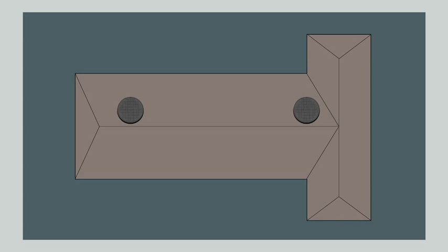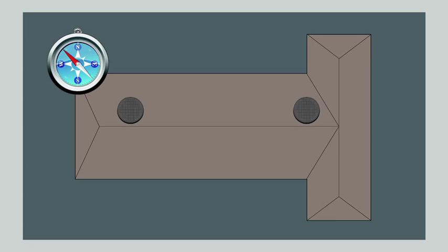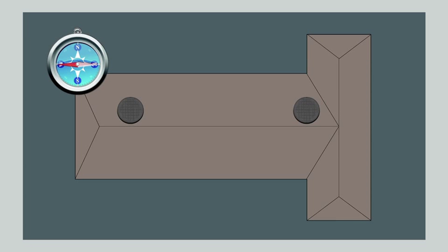The solar fan units are best placed as high as possible on a north facing facade. North east or north west are also acceptable losing only three to four percent solar efficiency. East and west facing facades are also acceptable but you will lose 15 to 20 percent of the solar efficiency of the solar fan.